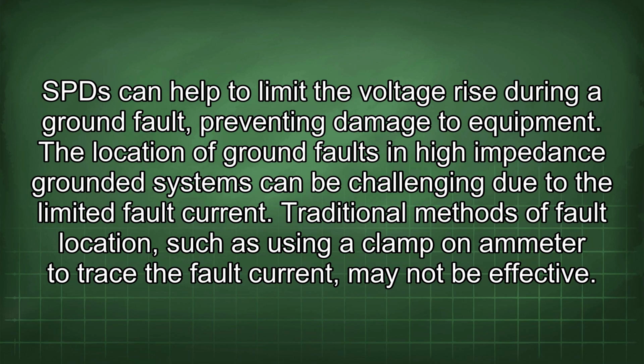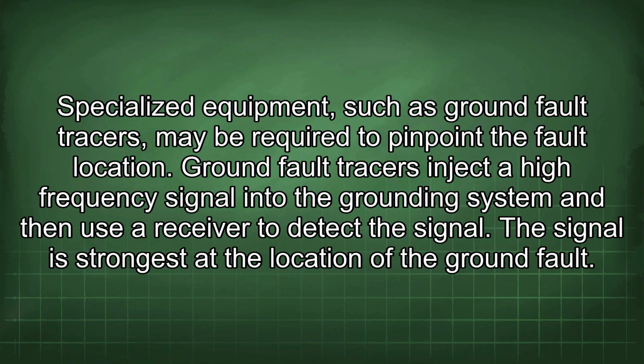The location of ground faults in high-impedance grounded systems can be challenging due to the limited fault current. Traditional methods of fault location, such as using a clamp-on ammeter to trace the fault current, may not be effective. Specialized equipment, such as ground fault tracers, may be required to pinpoint the fault location.